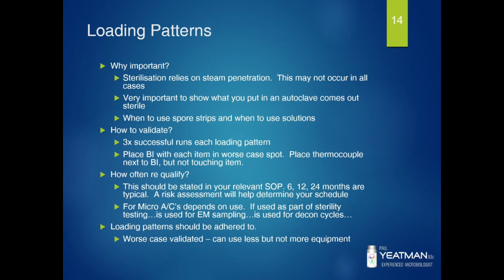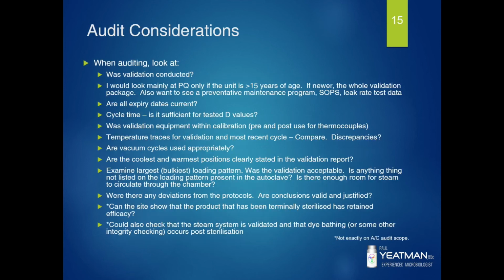And what would be a worst case sample? You've got to validate that specifically or pay specific attention to it. So a long tube, a cold spot, a large volume of liquid versus a solid chunk of metal. These could all be worst cases for your loading patterns, so you want to pay attention to those when you're doing your validation. Getting on to the fun stuff, once it's all validated, what are your audit considerations?